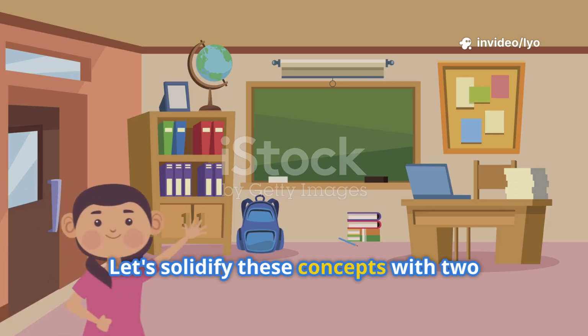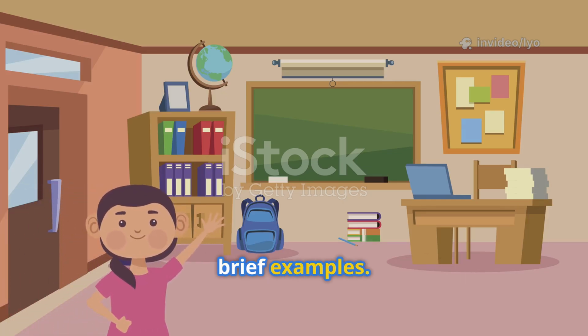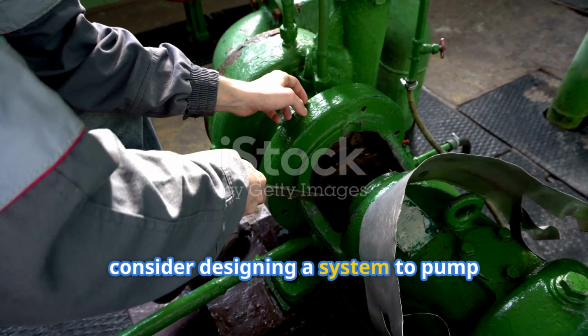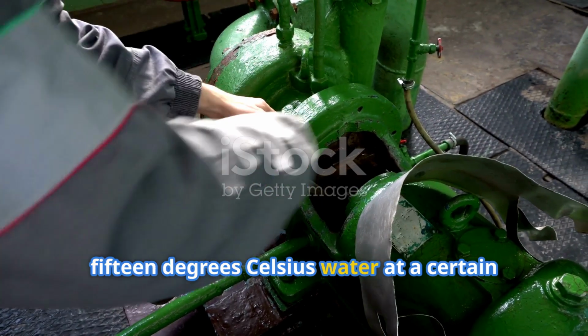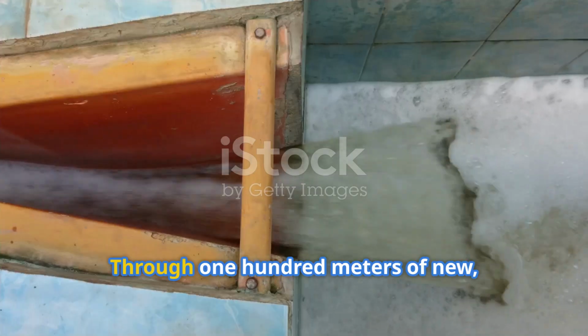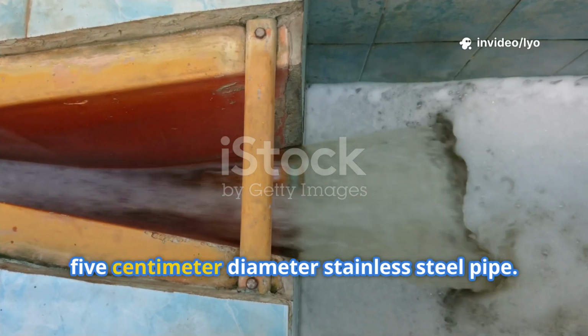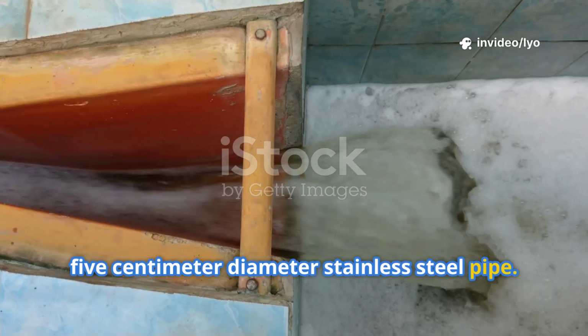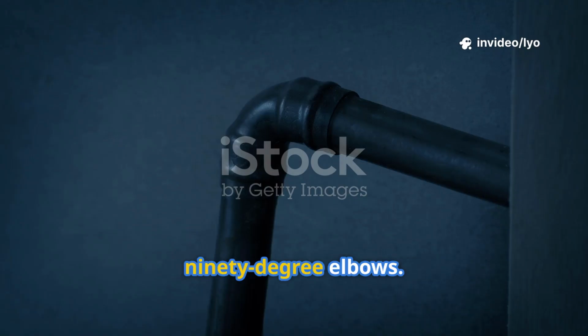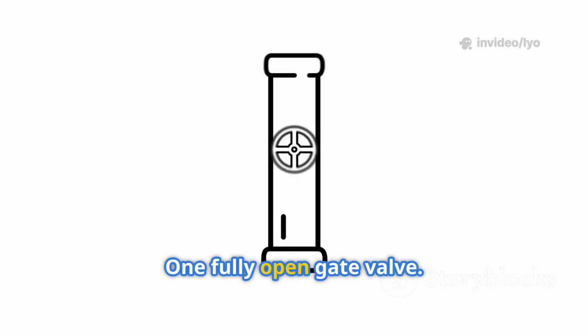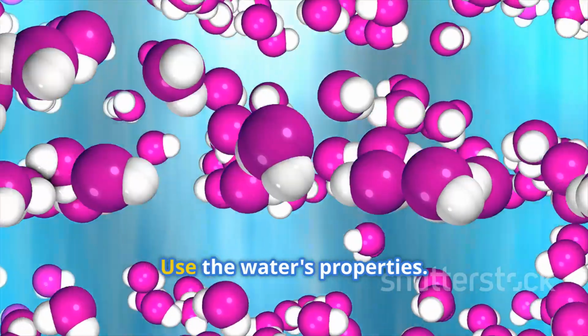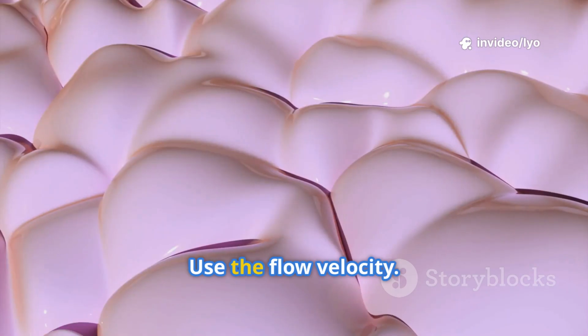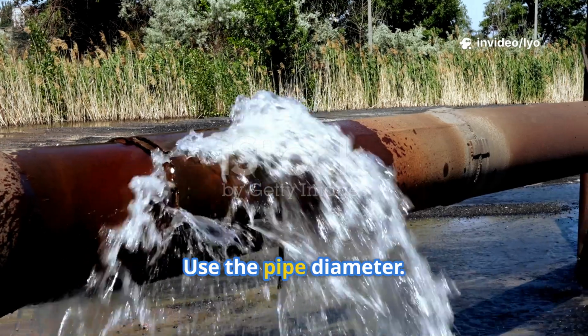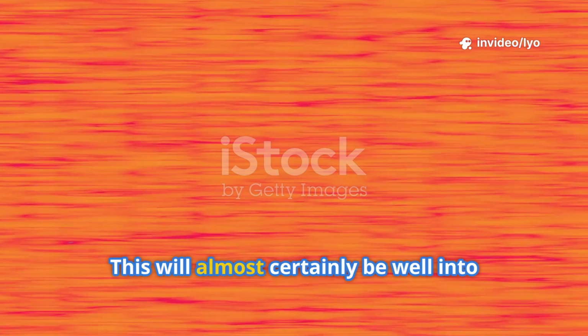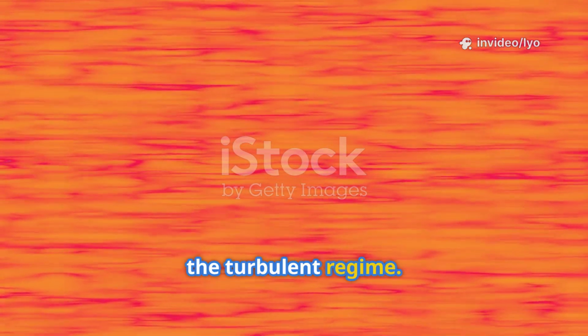Let's solidify these concepts with two brief examples. First, consider designing a system to pump 15 degrees Celsius water at a certain flow rate through 100 meters of new, 5-centimeter diameter stainless steel pipe. The system also includes two 90-degree elbows and one fully open gate valve. The first step is to calculate the Reynolds number. Use the water's properties, the flow velocity, and the pipe diameter. This will almost certainly be well into the turbulent regime.